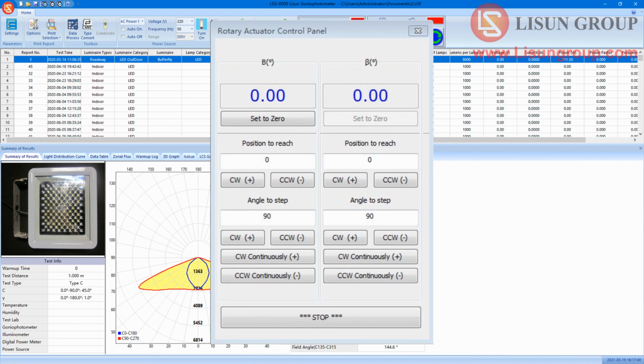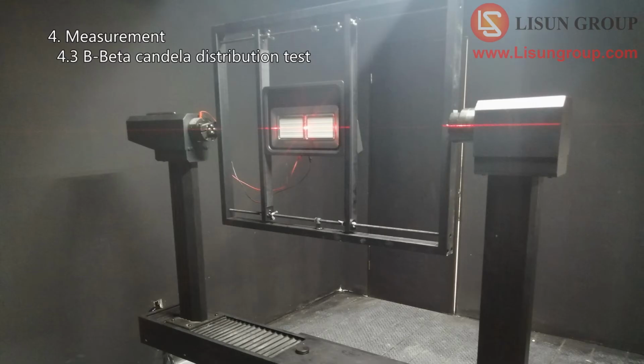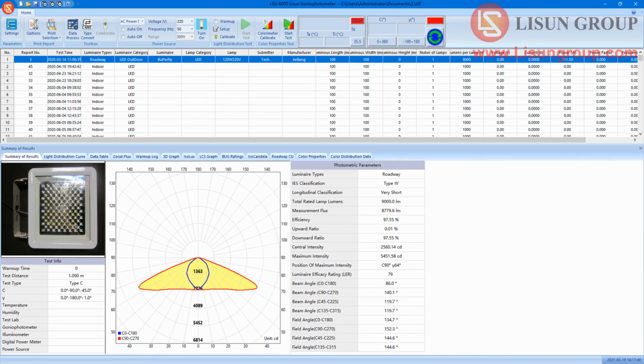Install the sample to the clamp, and the luminous surface should face the photodetector. To ensure that the luminous surface is in the center of the goniophotometer, you also need to rotate the beta angle to make the cross laser hit the luminous interface. And adjust the position of the sample to make sure that the cross laser hits the center of the luminous surface. Use the same method to turn on the sample. Click to enter the test settings.